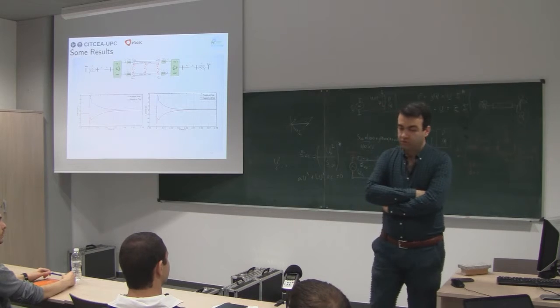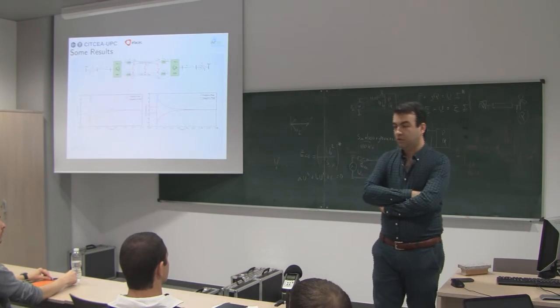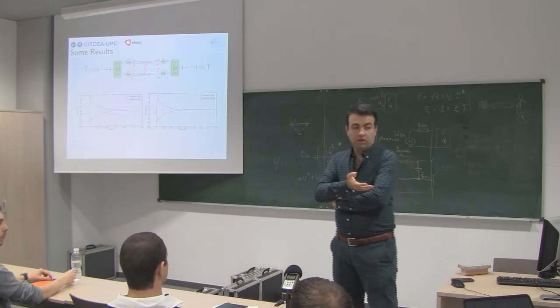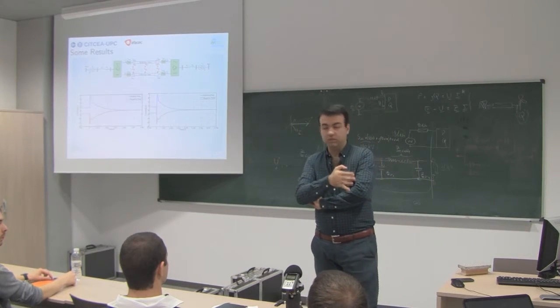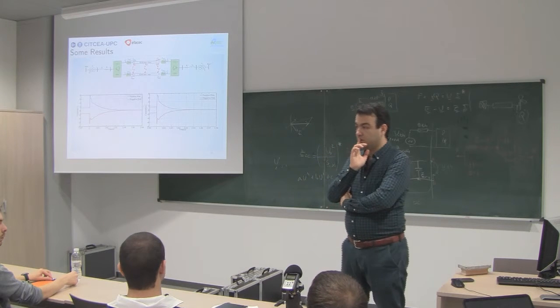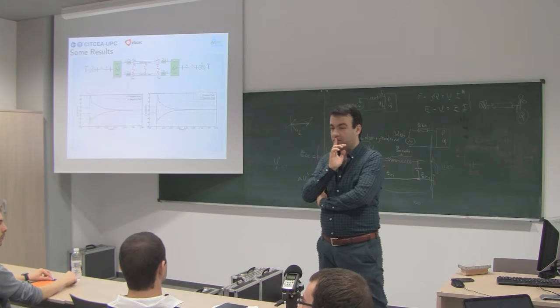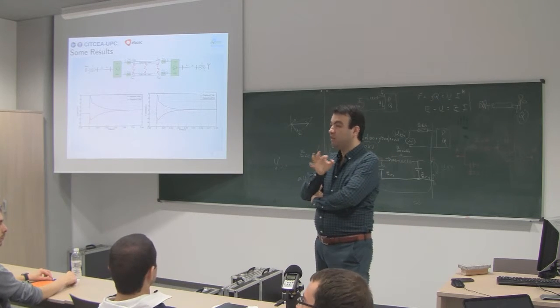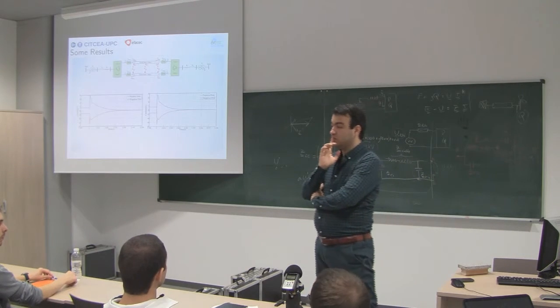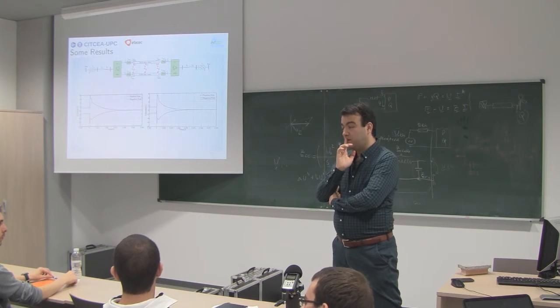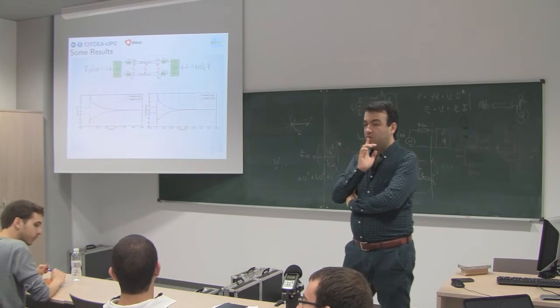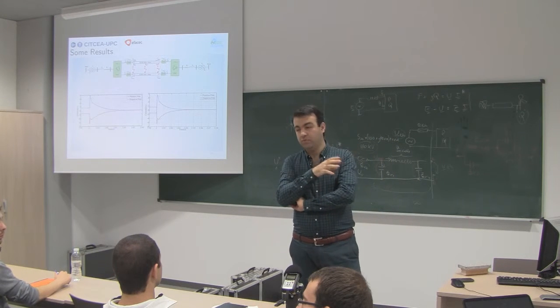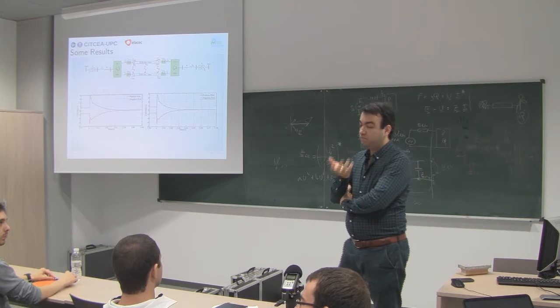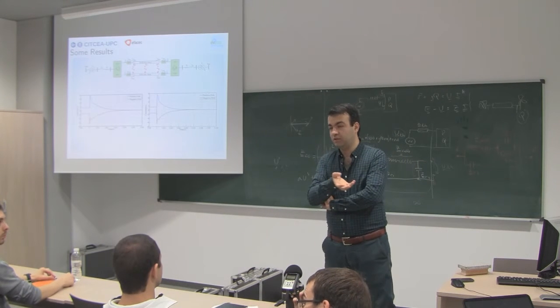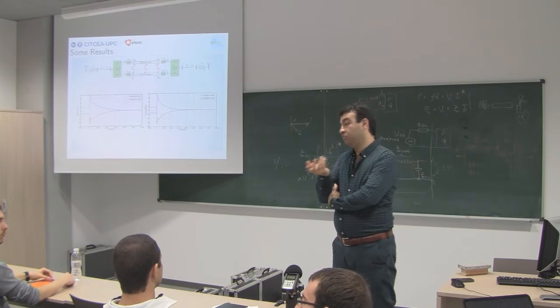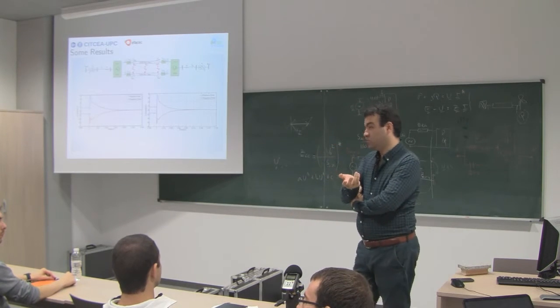No. You don't have any DC circuit breaker actually working in operation, I think. Maybe I heard that in China they want to integrate one HVDC circuit breaker into a 3 or 5 terminal grid that they are going to build. I think they have the 3 terminal, so they are going to have the 5 terminal one. But you don't have an HVDC breaker working in operation. So these are new technologies that we are talking about. And actually, even I cannot predict which one is going to be applied in future. But mainly, it seems that if we want a technology which can be adapted to an HVDC grid, it would be the hybrid HVDC circuit breaker technology.